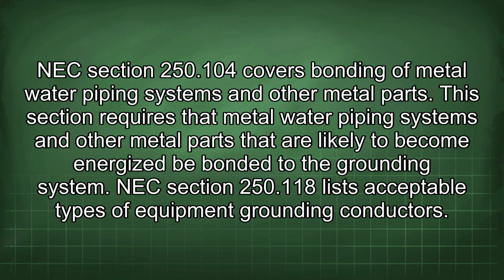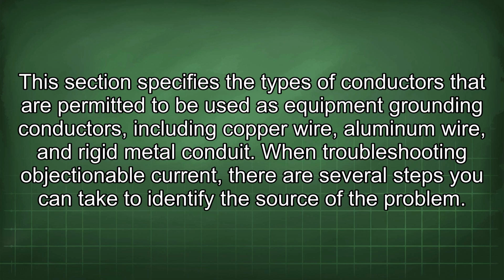NEC Section 250.104 covers bonding of metal water piping systems and other metal parts. This section requires that metal water piping systems and other metal parts that are likely to become energized be bonded to the grounding system. NEC Section 250.118 lists acceptable types of equipment grounding conductors. This section specifies the types of conductors that are permitted to be used as equipment grounding conductors, including copper wire, aluminum wire, and rigid metal conduit. When troubleshooting objectionable current, there are several steps you can take to identify the source of the problem.